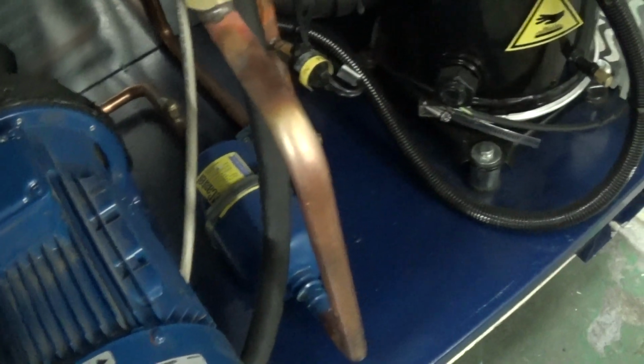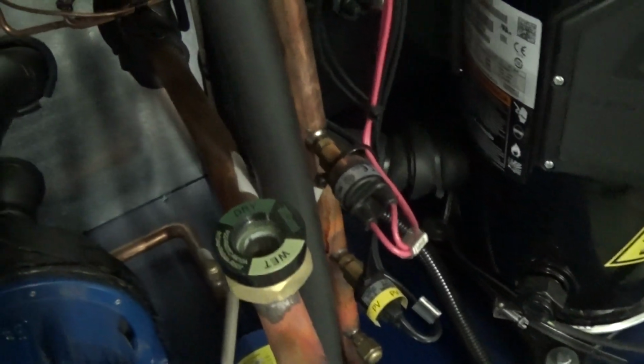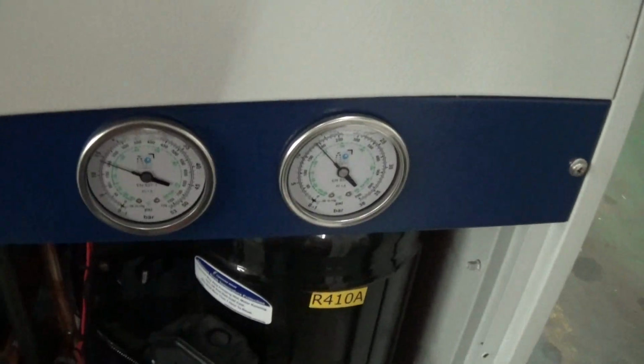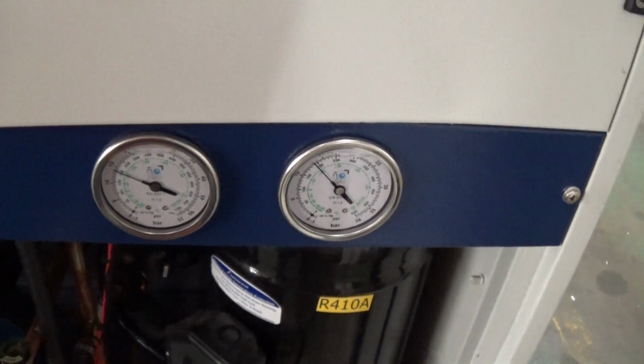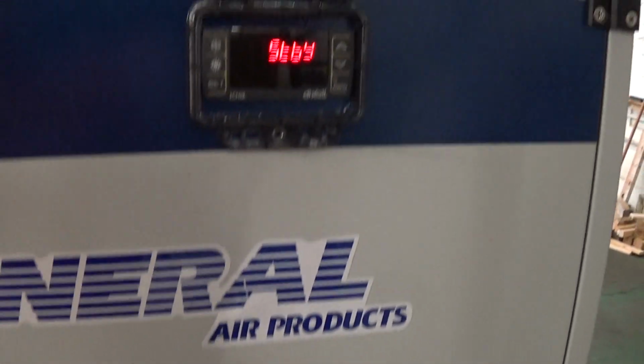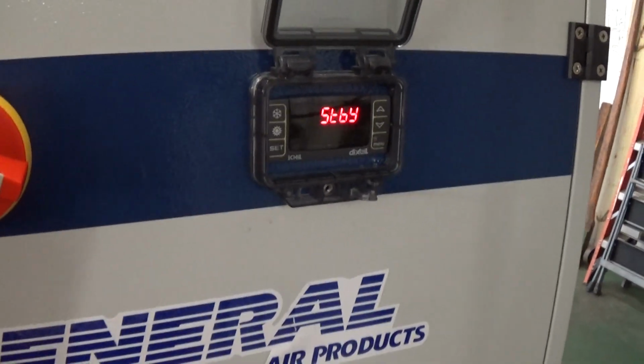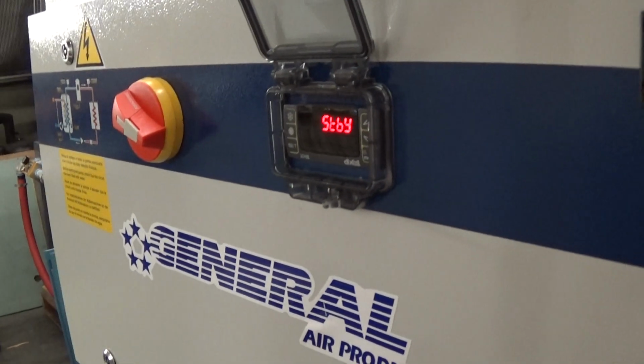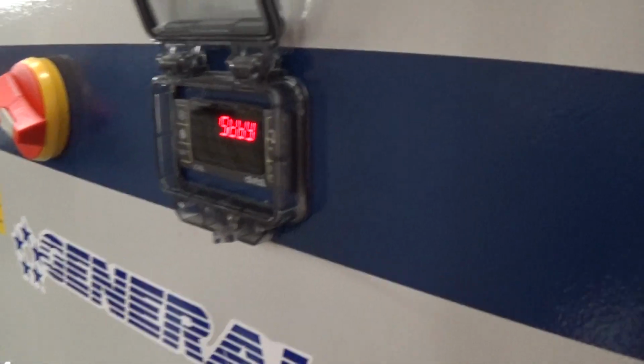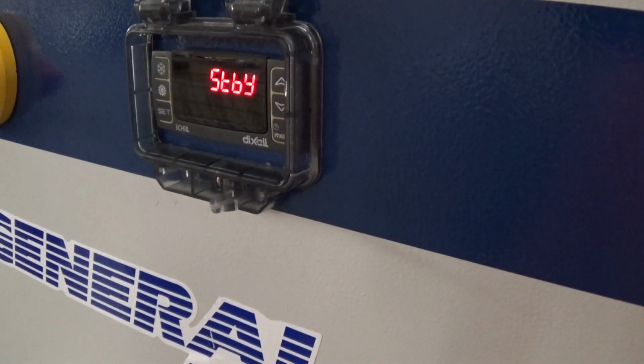It's got a nice hefty, approximately 3 horsepower centrifugal pump. You have your refrigerant dryer there, sight glass, pressure switches, thermal expansion valve. And you got one nice feature, and this is also your low and high refrigerant pressure gauges. Again, we've run this unit so I can run down to 20 Fahrenheit glycol in an outdoor environment. For 20 Fahrenheit glycol, I'd like to see 45% or 50% concentration. Don't go any higher, and definitely don't go much lower.